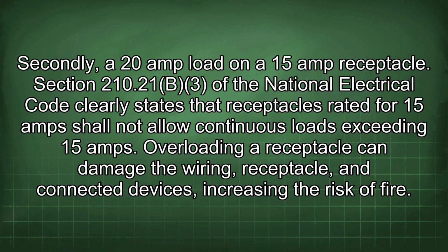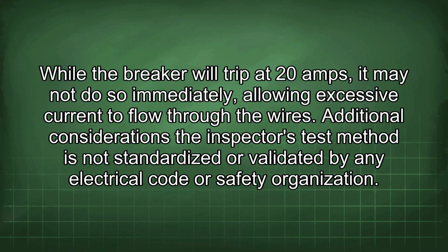Secondly, a 20 amp load on a 15 amp receptacle. Section 210.21(B)(3) of the National Electrical Code clearly states that receptacles rated for 15 amps shall not allow continuous loads exceeding 15 amps. Overloading a receptacle can damage the wiring, receptacle, and connected devices, increasing the risk of fire.